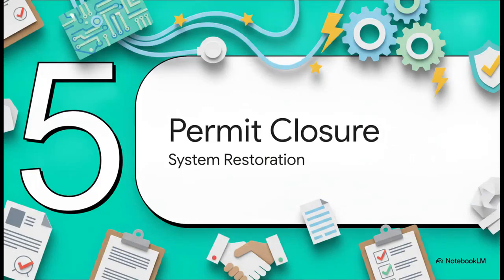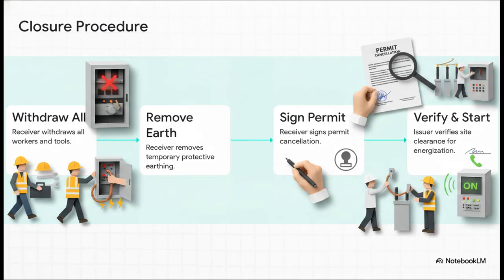And that brings us to the final stretch, Phase 5, Permit Closure and Energization. So, how do we get to that final ready for energization state? Well, closing the permit is just as strict as opening it. First, the receiver has to physically withdraw every worker, tool, and scrap of temporary material from the site. Second, they remove the portable protective earthing. Third, they actually sign the permit cancellation, officially declaring the equipment is no longer safe to touch. And finally, the issuer steps back in. They check that signature, visually verify the site is clear, remove the main grounding, and only then do they call the control engineer to bring the system to life.